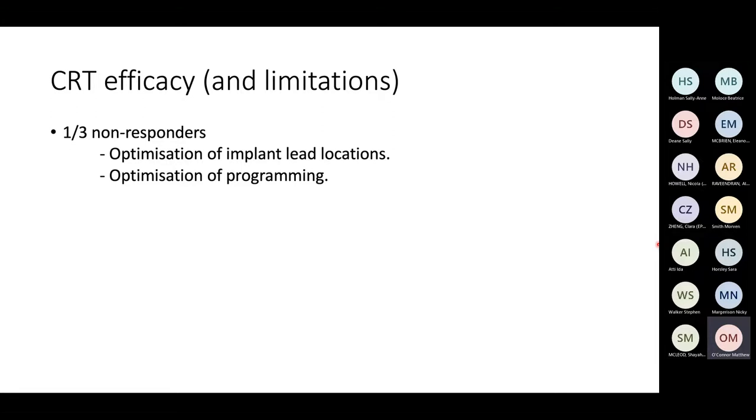Those who don't respond, you can try and optimize the lead position. So sort of those few factors we were talking about before. And you can change the programming of the device to make some difference. Often it only makes very minor differences. It doesn't usually change someone from a non-responder to a super responder, but it might improve things very slightly.